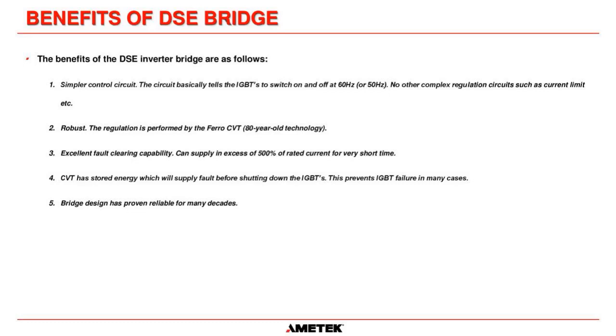The transformer does all of the magic. All we do in our MicroFerro systems, whether it's a DSE or the old SE, is switch on and off at 60 hertz. Simple as that. They are robust. The regulation is performed by the Ferro CVT, the constant voltage transformer, and it's 80-year-old technology. It's just so reliable.